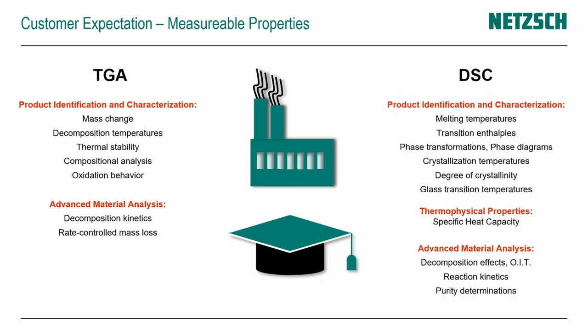Before we come to the methods and instruments, let's have a general look at what we expect from TGA and DSC analysis. For TGA analysis, we typically talk about material properties like mass change, decomposition temperatures, and thermal stability — all properties which identify or characterize products. TGA also allows advanced material analysis like, for instance, the analysis of the kinetics of a decomposition reaction.